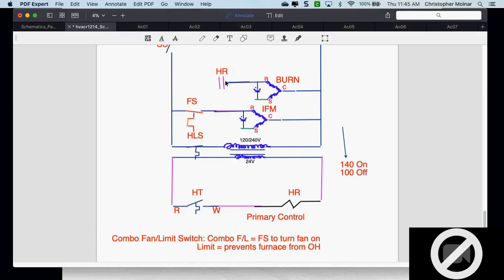Okay, so they used to take out the entire low voltage side of my wiring. What happens to your thermostats? Turns off. Yeah. Okay. This becomes a problem. Because if I have a regular thermostat without a digital display or a digital thermostat with batteries, the homeowner will never notice. But if I have a digital display thermostat that relies on that transformer, and if it's wired this way, what is the homeowner going to see every time that limit switch opens? It would kind of reset the thermostat. It's going to reset the thermostat. Would that drive you nuts as a homeowner? Yeah. Yep. Oh, yeah.